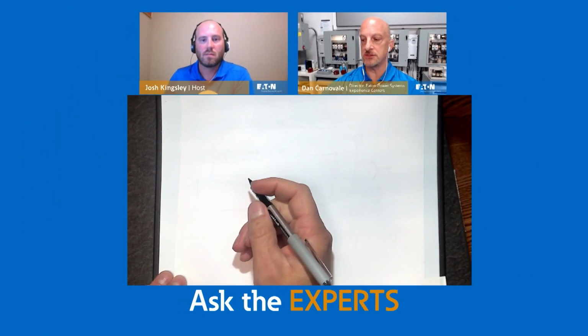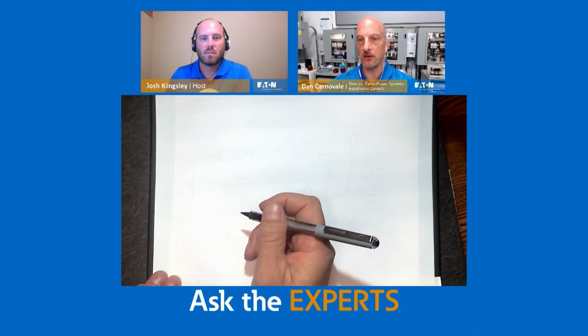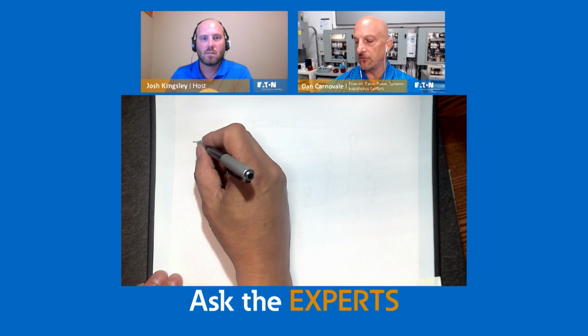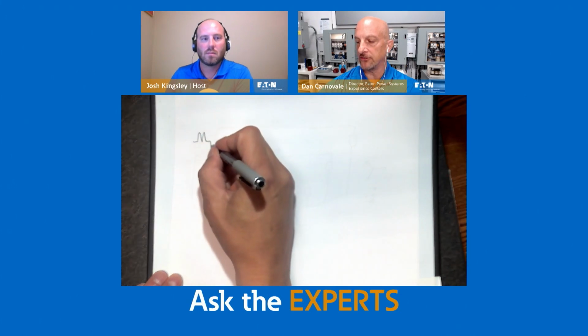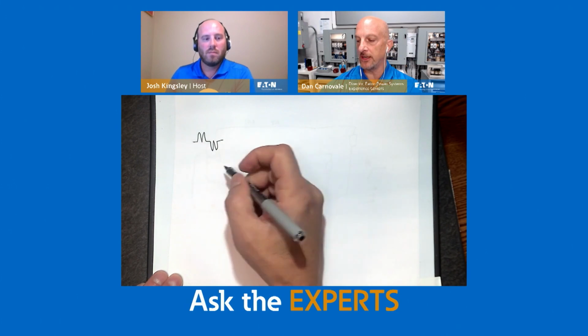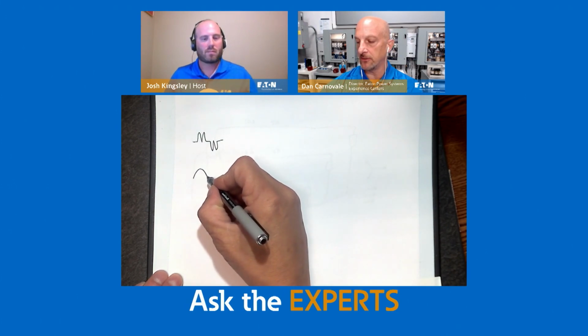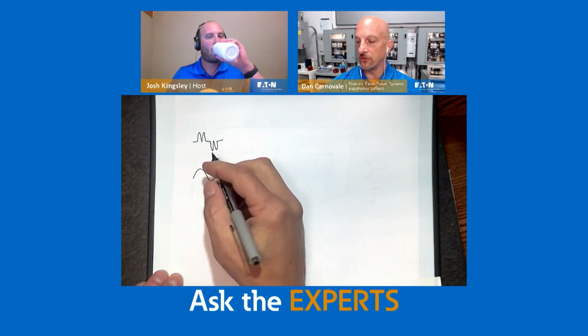Yeah. Hey, Ardeth, that's a really good question. Whether it's a drive or really any electronic load, let's say, again, LED lights or whatever, we say that those electronic loads have characteristic harmonics. So I've been drawing this current that looks like this, and I'm going to back up a little bit and explain that a little more. This current has a 60 Hertz component, and it has other frequencies that, added together with superposition, add up to be that waveform.